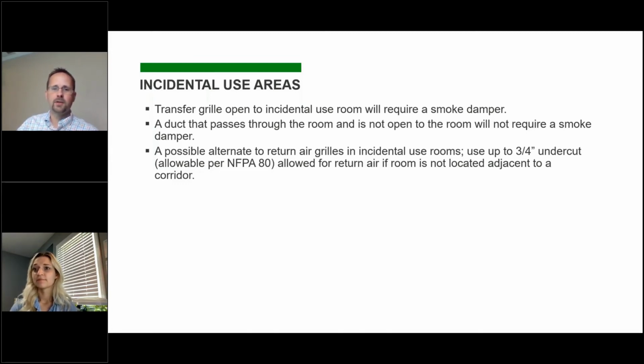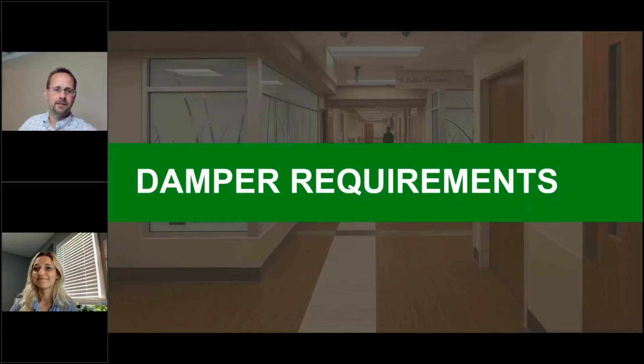So if you do have a return air plenum and have one of these spaces, it's important to look into that and try to avoid having a true transfer air duct if you can. That's probably best if it's a really small room. But that smoke damper portion is missed quite a bit, and it isn't really obvious in the way the code's written. It would be nice if it was changed to make that a little bit more obvious.